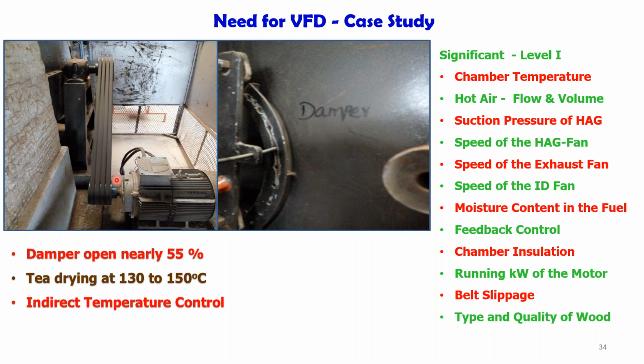Moreover, this VFD is going to be closed loop only, because you always sense the temperature, and based on the temperature the speed of the motor keeps changing. So you yourself need not change it. If it is an open loop type, then there is no need to go for a VFD. It should be a closed loop type, sensing the temperature, sensing the flow of the blower, and sensing the temperature of the blower. Based on that, the feedback will be given to the motor.